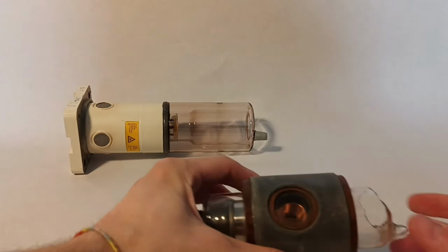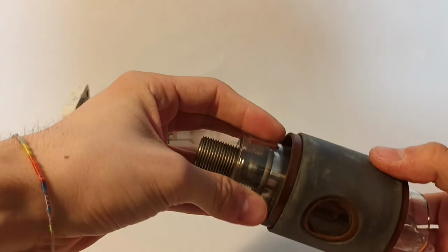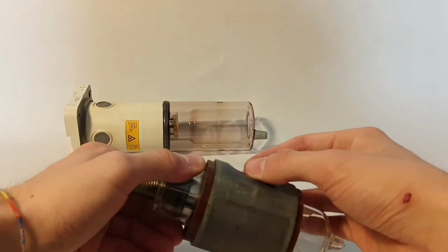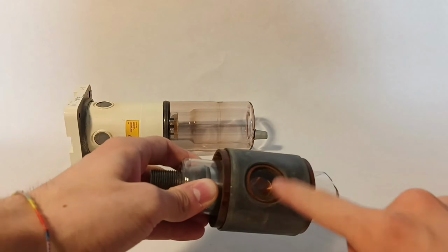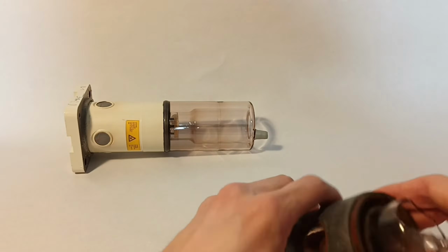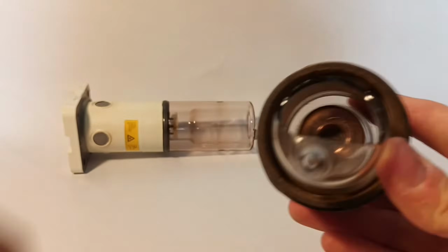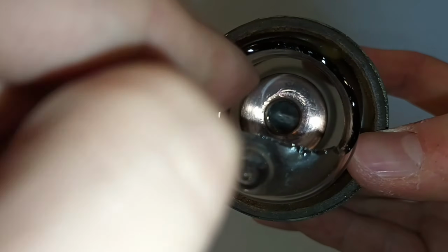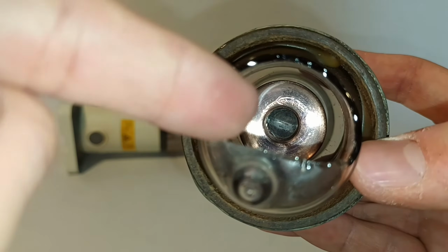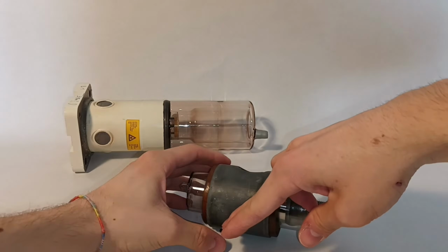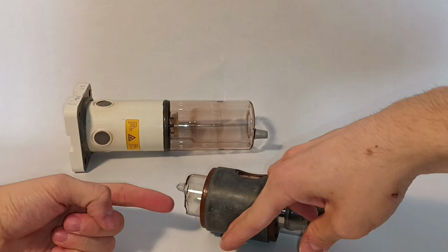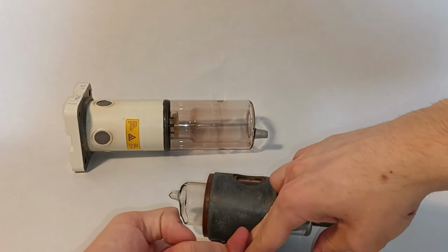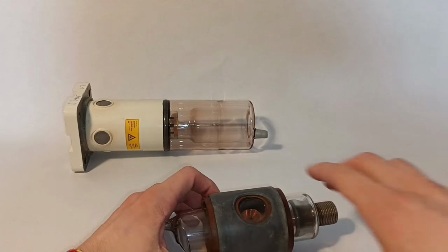It consists of a glass envelope surrounded by this lead foil, which prevents radiation from scattering around in other directions, aside from the one that we want, that is this little window here. Inside we can find the anode, which is the part of the tube subject to a high voltage potential to accelerate the electrons. That you can see there, which is the round part, and inside there is a button of tungsten. When electrons that are created here accelerate because of the high potential, they strike the anode and emit the X-rays in this direction, which comes out of the window here.